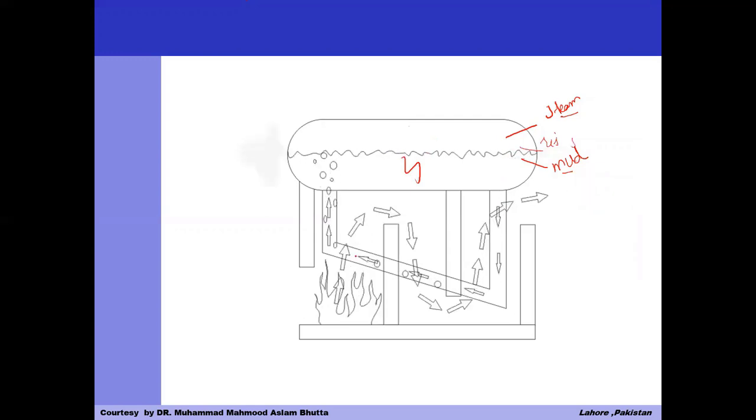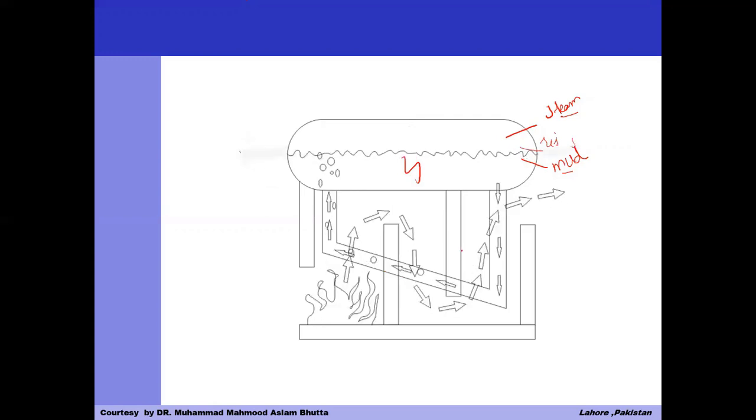Water in the lower drum and in the riser is heated and steam is produced, which comes to the upper drum naturally. In the upper drum, the steam is separated from the water naturally and stored above the water surface because of the change in density. Colder water is fed from the feed water inlet at the upper drum, and this water is heavier than the hotter water of the lower drum and the riser.